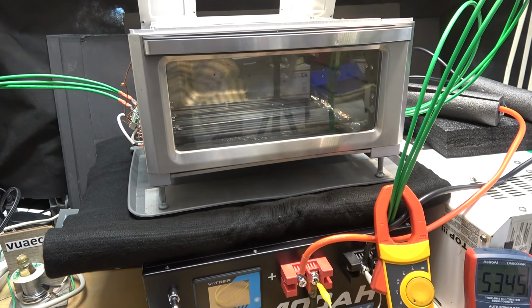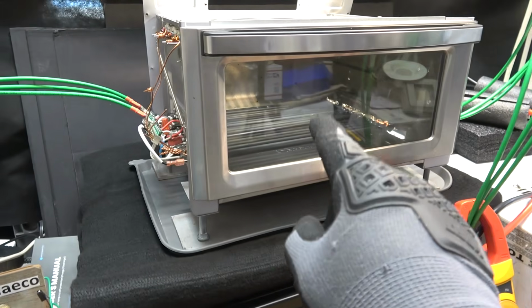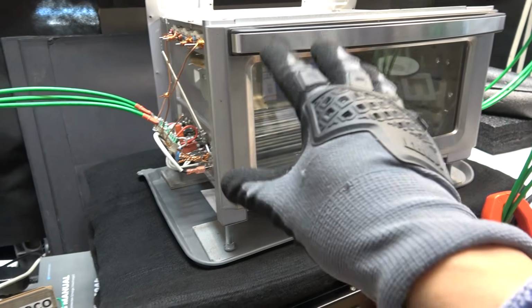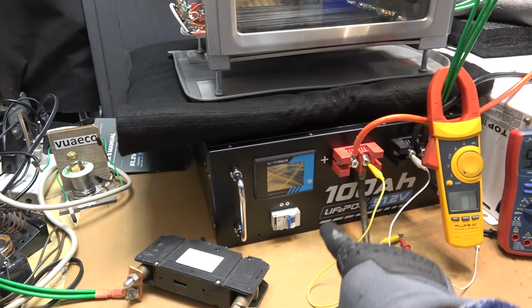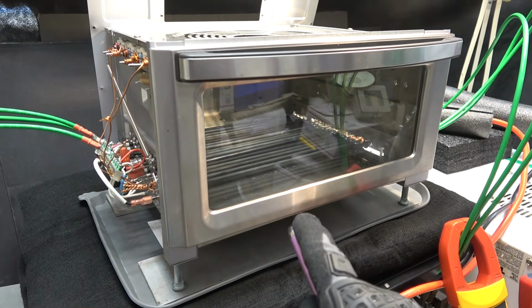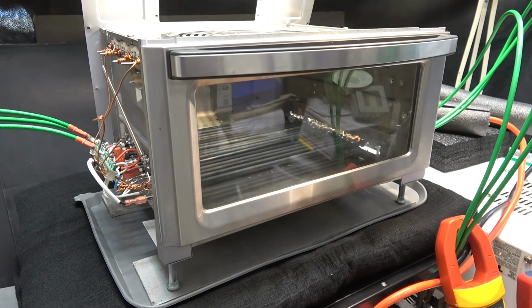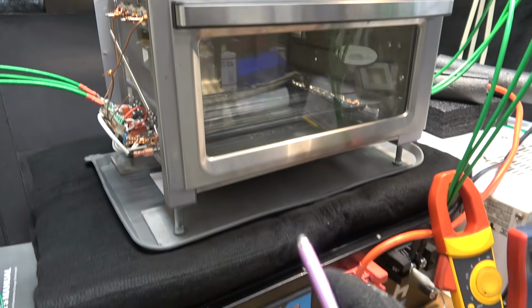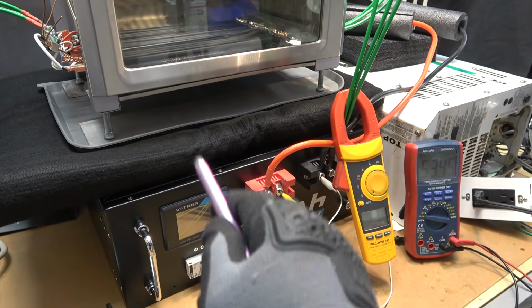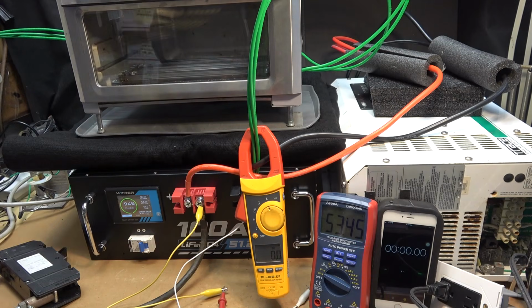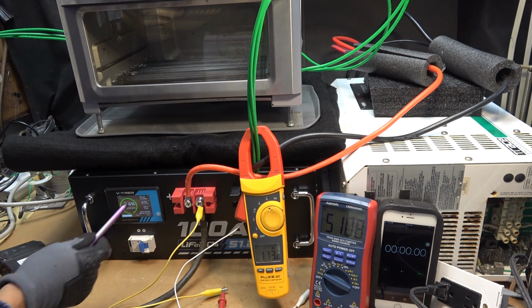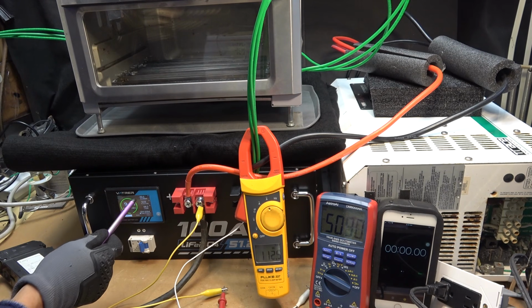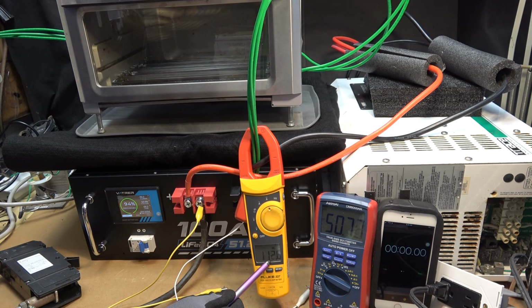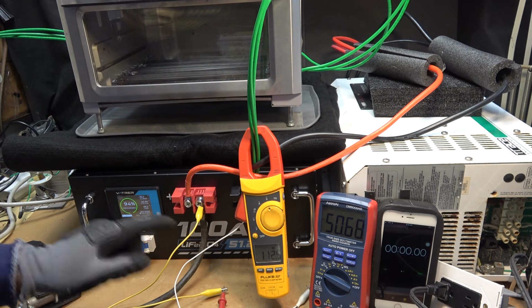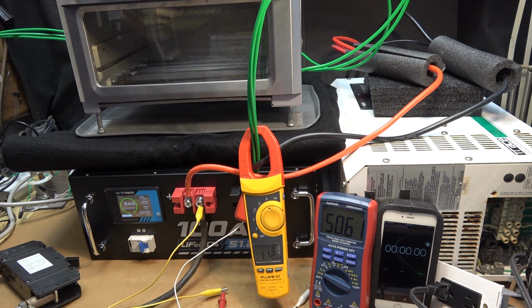Let's push it to the limit, shall we? I've got my 48 volt DC stove and it's connected directly to the battery. This stove here runs at 110 amps and that will exceed the limit of this battery, which is 100 amp continuous. Now let's turn it on. 114 amps on the screen, 112.7. So that is very accurate.